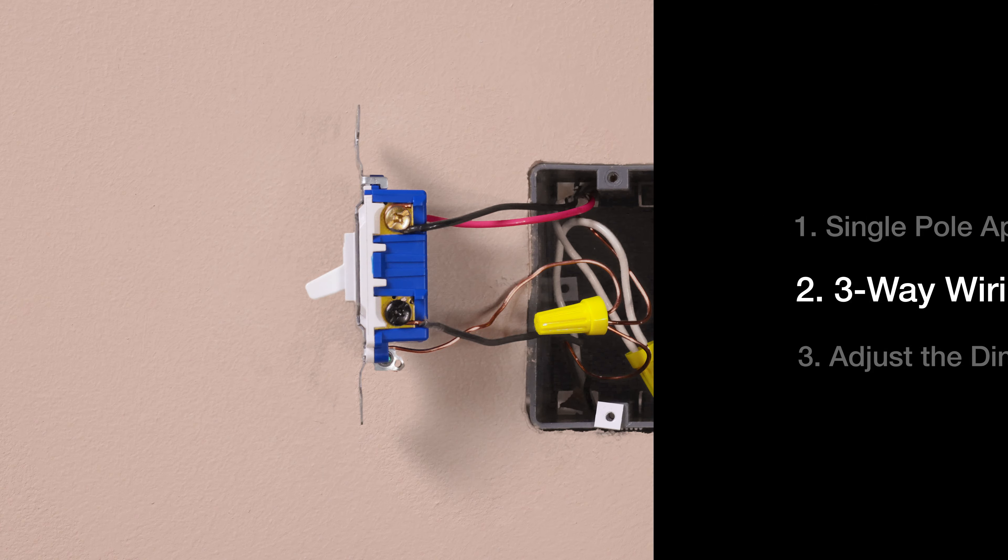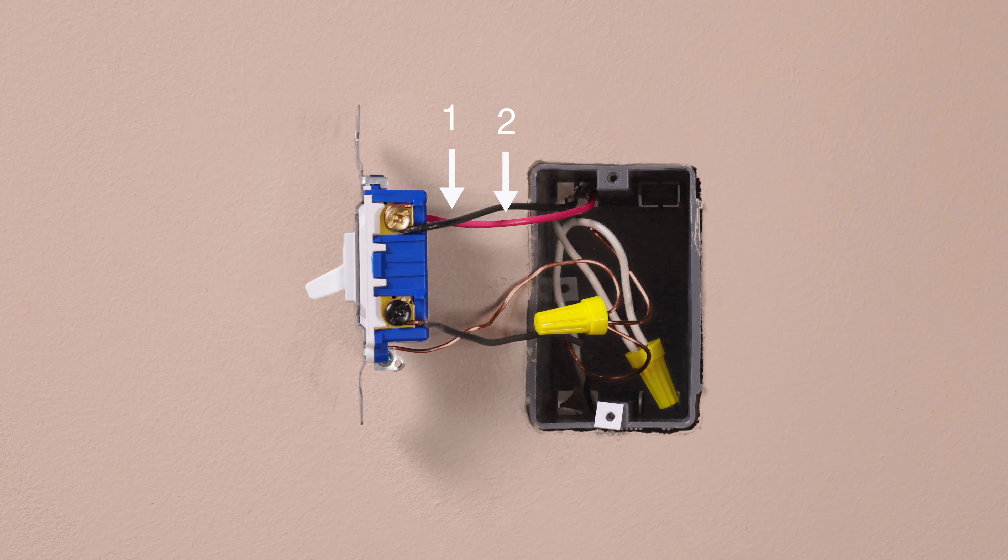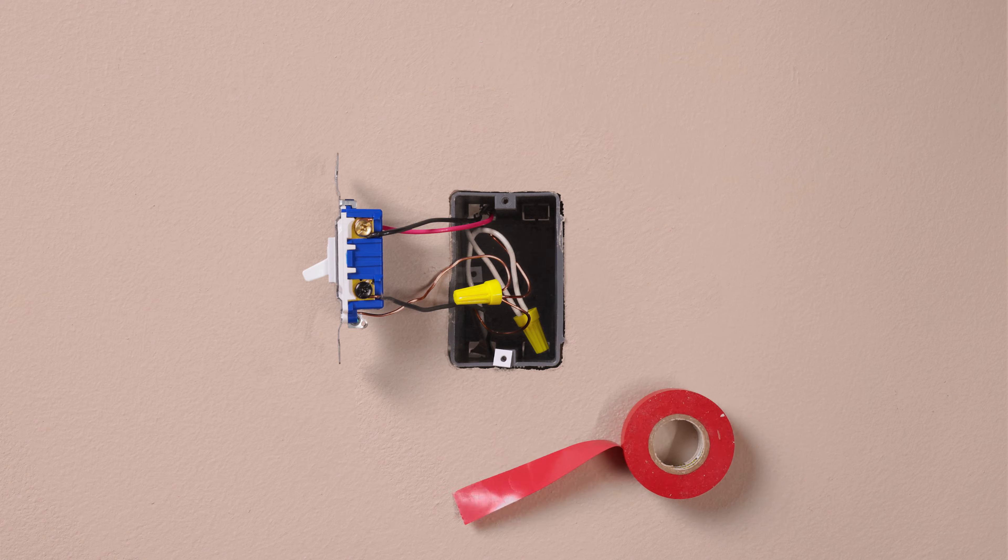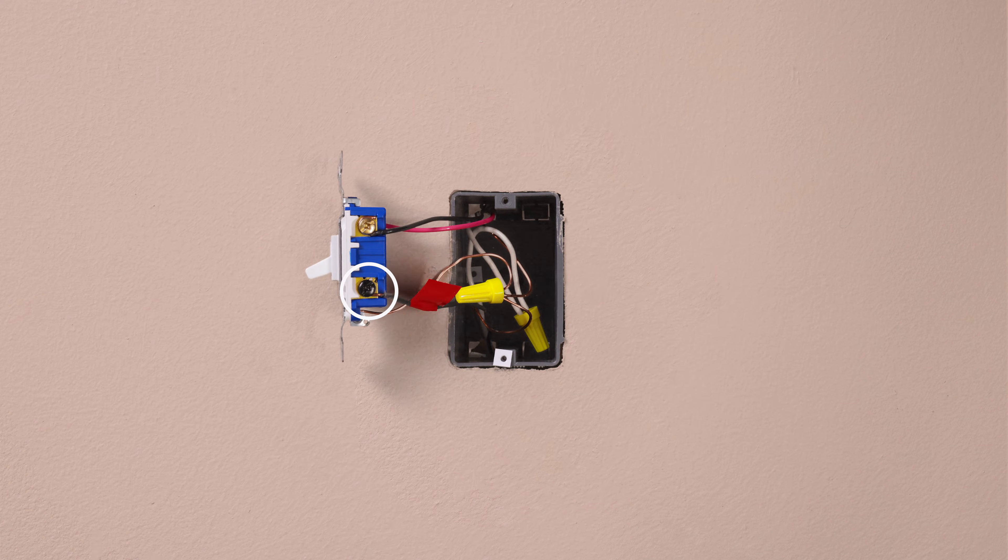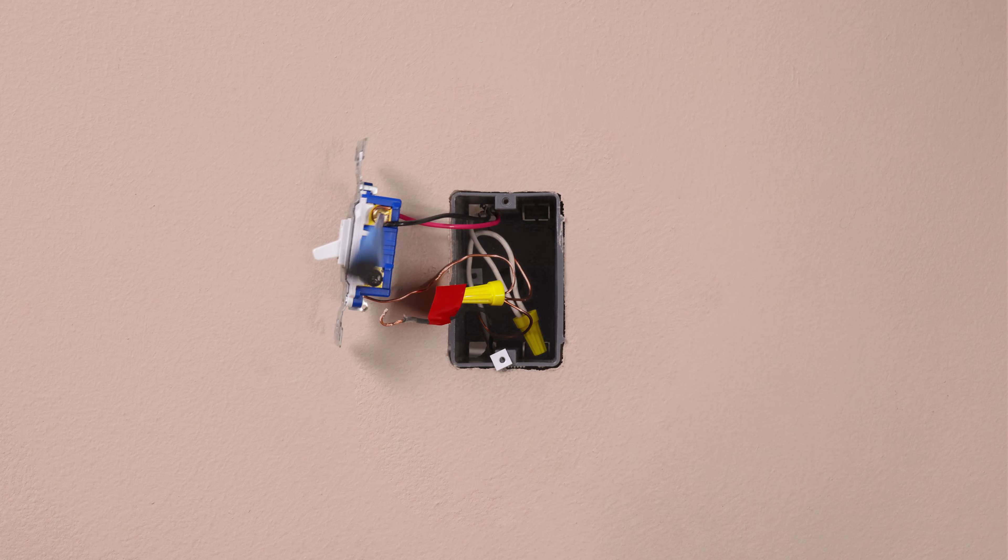To install this dimmer in a three-way, you should have three wires plus a ground connected to your old switch. Before removing your old switch, take a piece of electrical tape and tag the wire connected to the different colored screw of the existing switch. This is typically a black wire. Then disconnect and remove the switch.